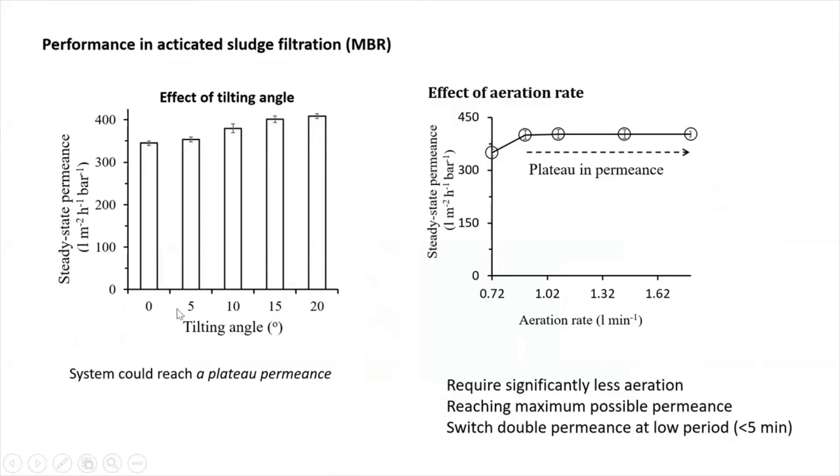We tested for an MBR application. As you can see here, zero means you have vertical modules. If we tilt it up to, let's say, 20 degrees, you can achieve significant increment of the permeability. And then even up to some point, if you manipulate the aeration, you can reach a plateau permeance. The plateau permeance means the maximum permeability you can achieve where there is no fouling in our systems.